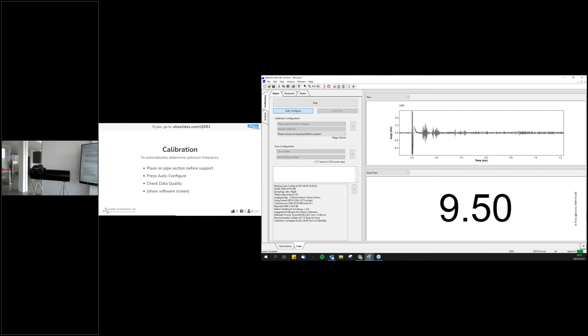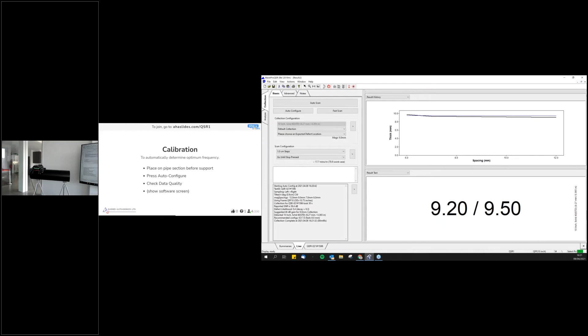All right, so if you look on the bottom left of the screen, you can see that the calibration step took only 49 seconds. And the QSR1 has recommended these two spacings to be the optimum. That means that there are certain frequencies that correlate to these spacings. Notice that during the setup, I did not input any information regarding the pipe size. The software has automatically detected that it's a schedule 40 pipe, and the nominal wall thickness should be 9.27 millimeters.